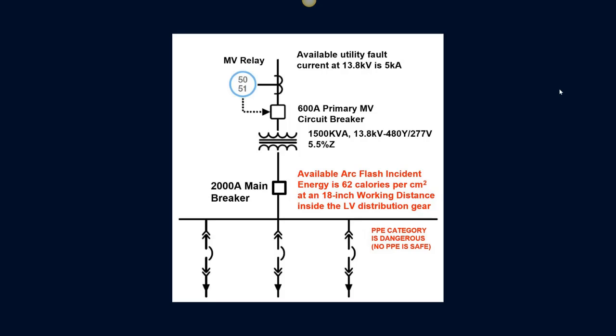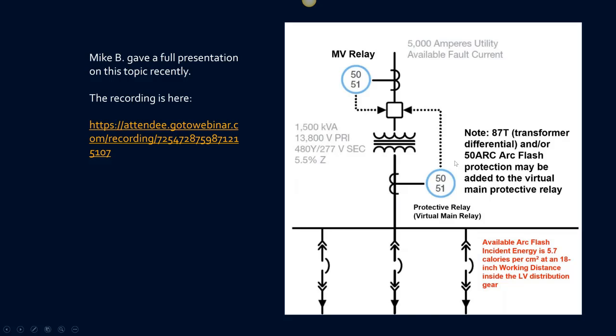and so the elimination of that main breaker and replacing it with a secondary virtual main not only saves that real estate, but it also makes for a safer system for all of the feeder breakers as well. So if we're close coupled here, this is both the main and the feeder in the same gear. In this example, the equipment would be 62 calories per centimeter squared, meaning no PPE is ever safe while that equipment is energized and at the IEEE 1584 18-inch working distance. So the alternative to this, the space-saving and safety benefit alternative, and next slide, please, Michael, is to implement a secondary virtual main.